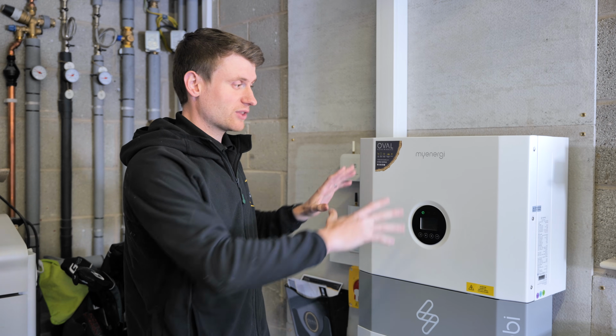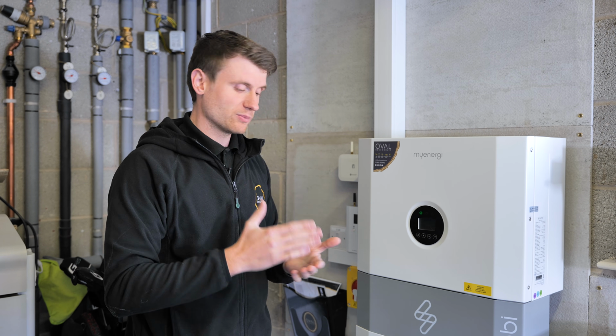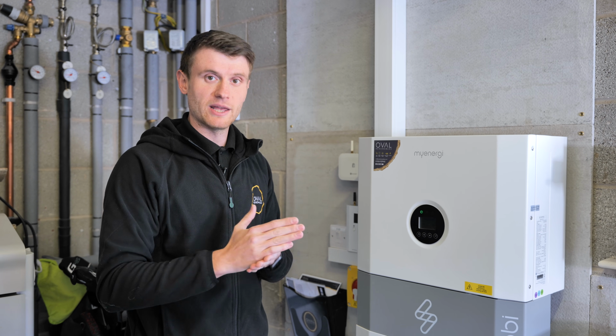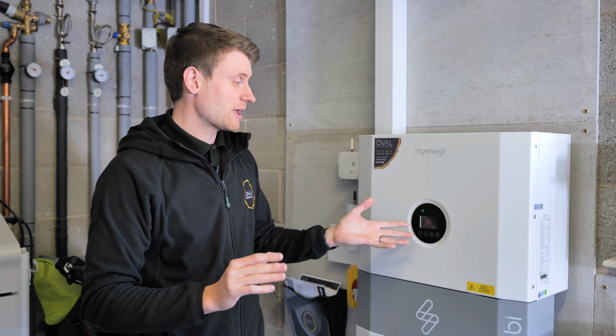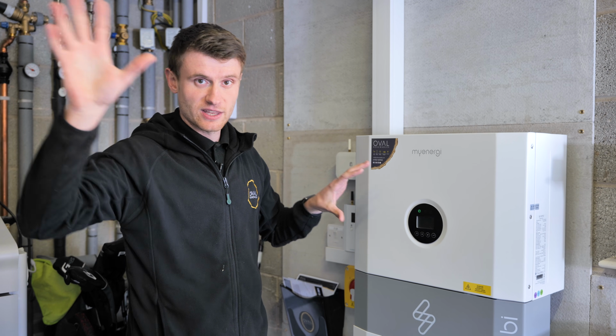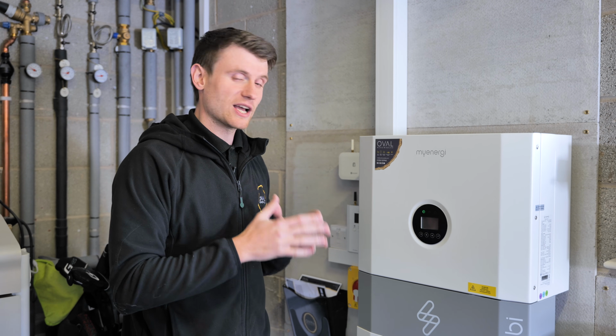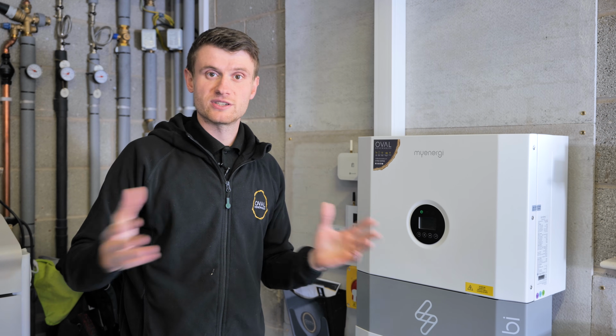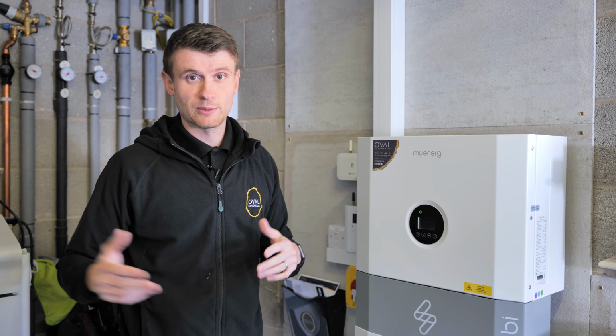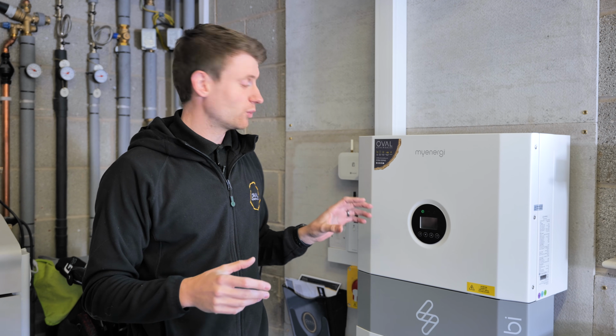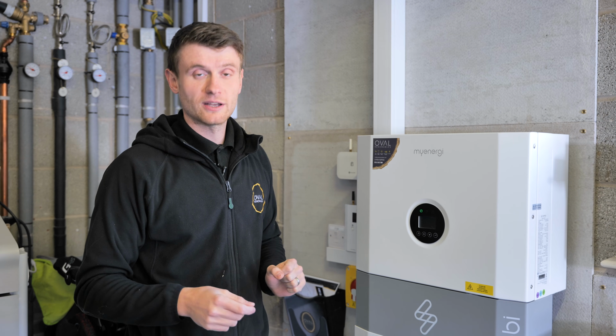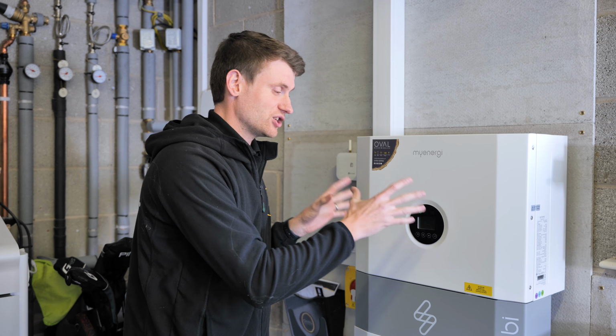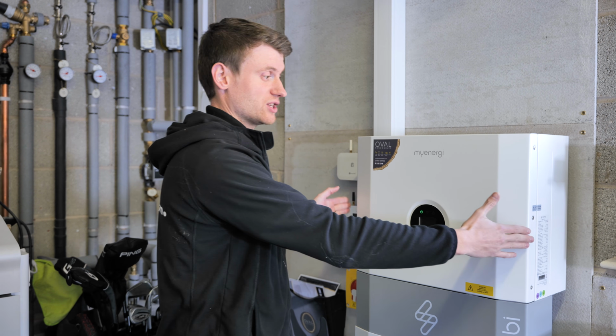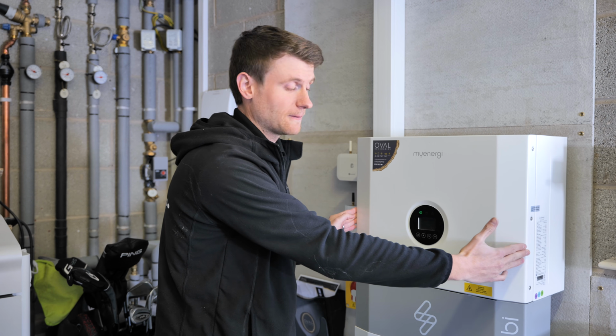So you're allowed that system, but there is something we call an export limit that they want you to put on the system. They might say you can have the system you're proposing, but we want you to export limit this site to 3.6 kilowatts, 4 kilowatts, 2 kilowatts, whatever. That's just something we input through the Libbi controller, and it means that if that energy is needed in the house, this could discharge at a full rate of 5 kilowatts.